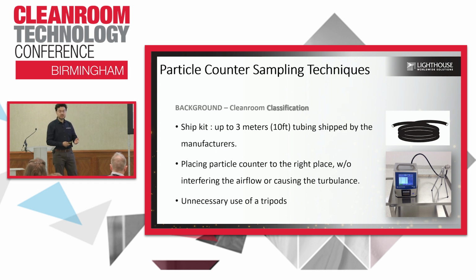And placing the particle counter in the right place without interfering with the airflow and causing turbulence is another issue in the background. And the unnecessary use of tripods. This picture, our marketing team created a very nice looking setup. In fact, this is wrong, because if you have this kind of a cart, then the best idea is to put the isokinetic probe directly on top of it.